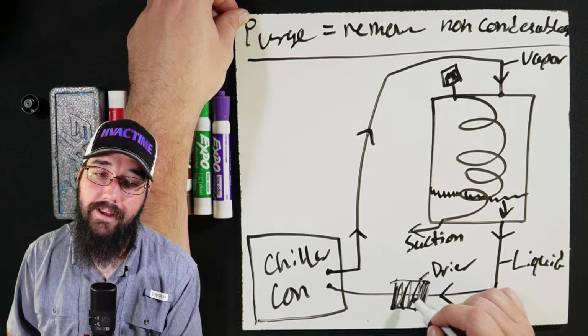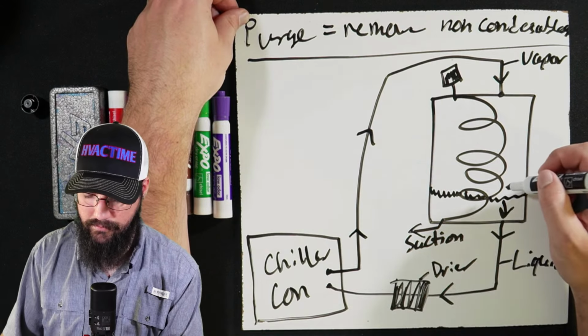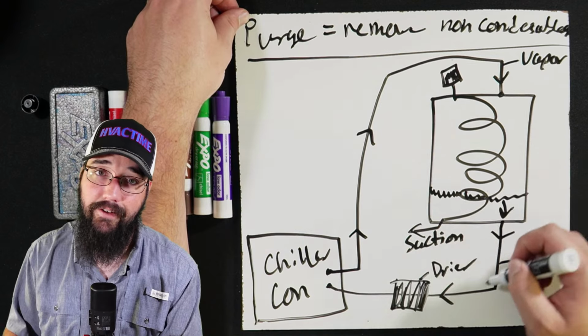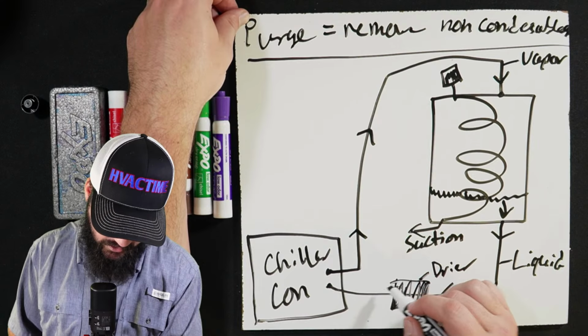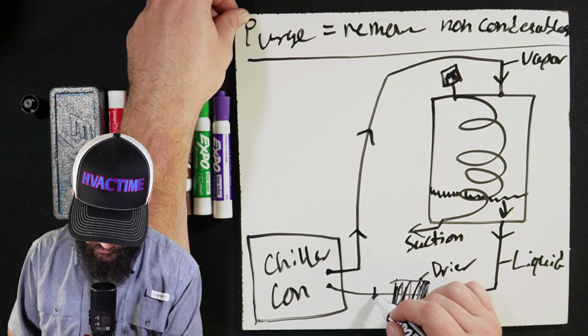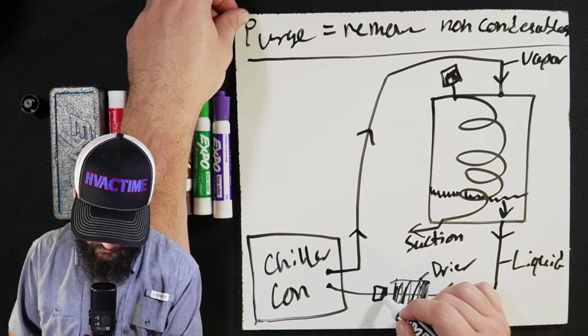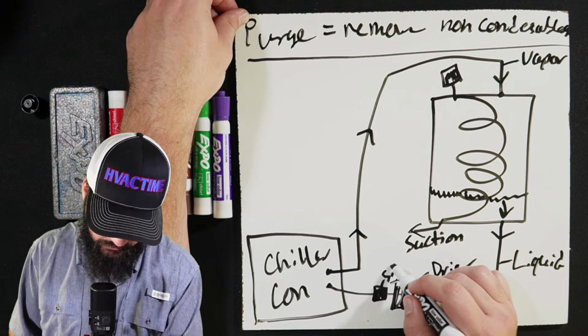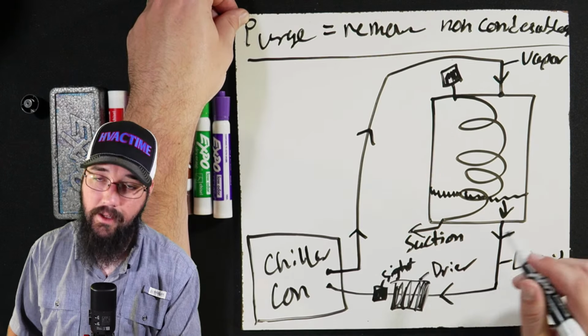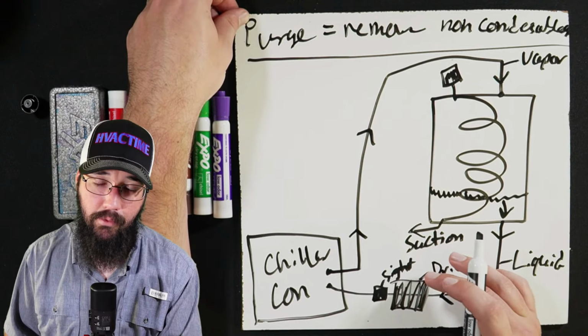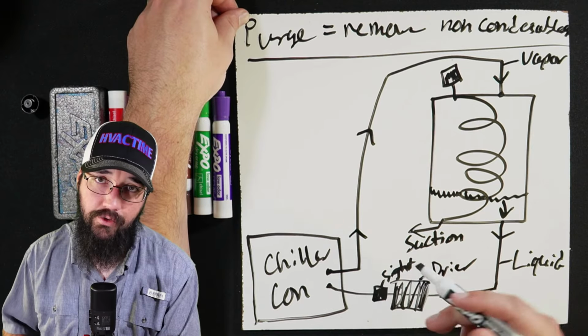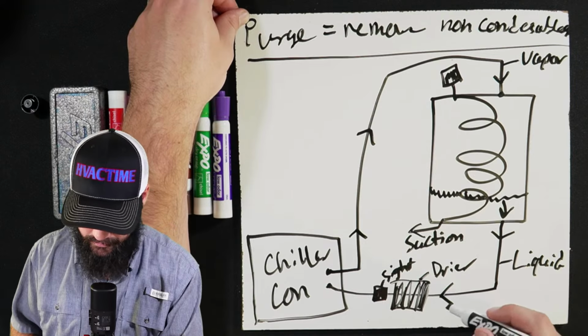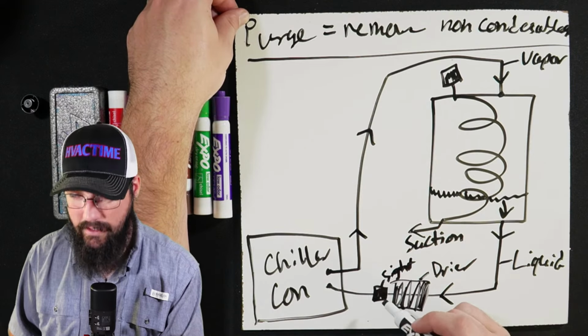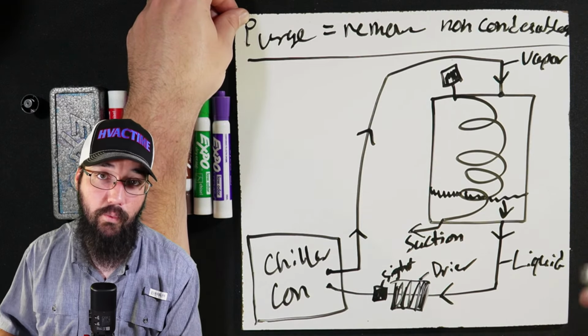This is meant to capture the moisture that is being condensed here. These dryers will very commonly have a moisture indicator or a sight glass of some kind somewhere. Not always, but very common. If it doesn't, I recommend adding one at some point, just so you can see the physical condition of that liquid leaving and have a moisture indicator to tell you how wet it is.